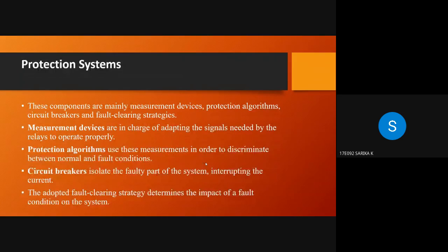There are three main components in protection systems. Those are measurement devices, protection algorithms, and circuit breakers. Measurement devices are in charge of adapting the signals needed by the relays to operate properly. Protection algorithms use these measurements in order to discriminate between normal and fault conditions. Circuit breakers isolate the faulty part of the system, interrupting the current. The adopted fault clearing strategy determines the impact of a fault condition on the system.